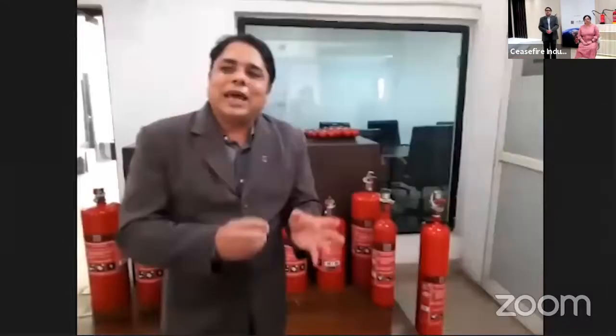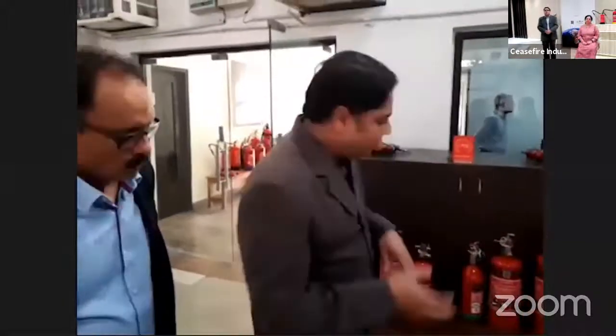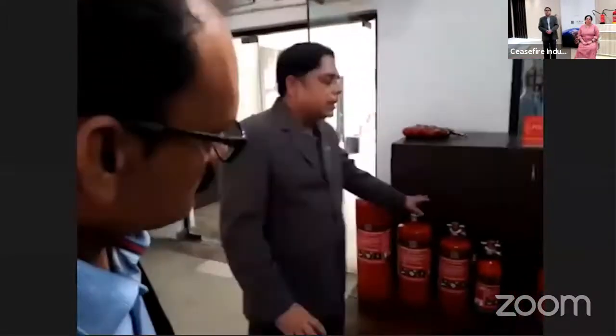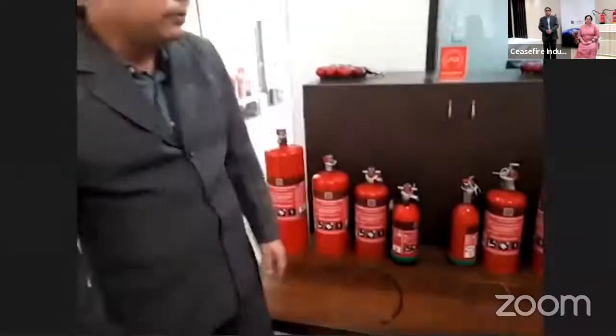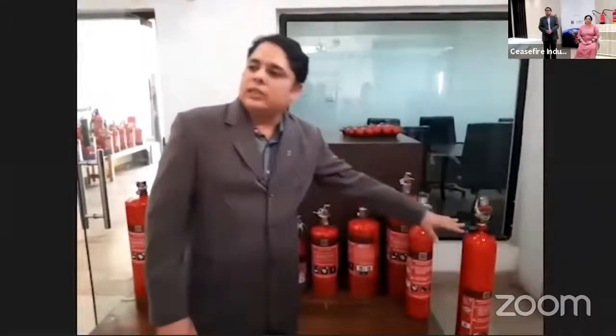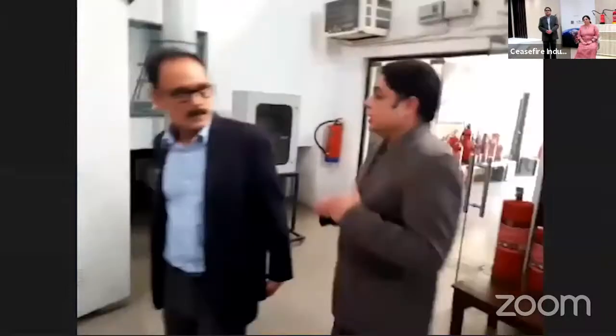There is another partition, besides direct and indirect, called the low pressure and the high pressure system. This is only about how the gas is stored within the cylinder. If it's a gaseous system at 15 bar, it is called the low pressure system. And if it's CO2, which is stored at high pressure, we have 2 and 5 kg CO2 cylinders. Since we have already explained the system, why don't we see the live installation so that they will understand it better? Very well, Akash.